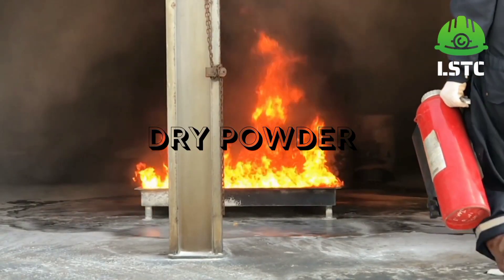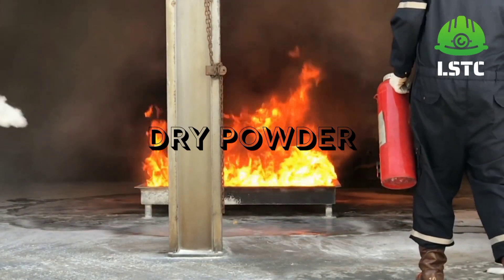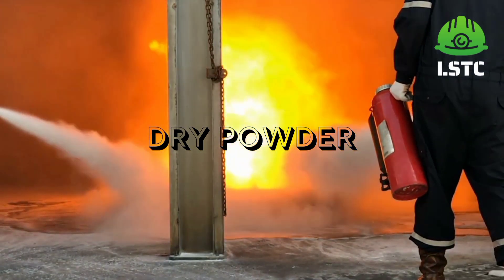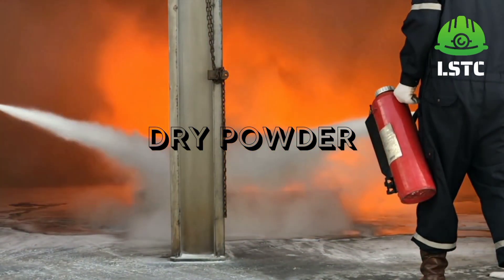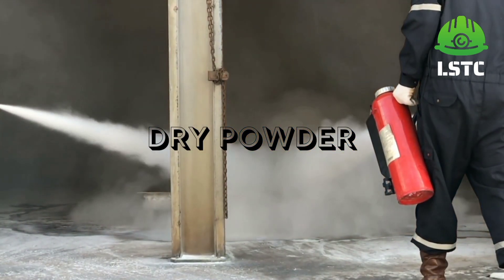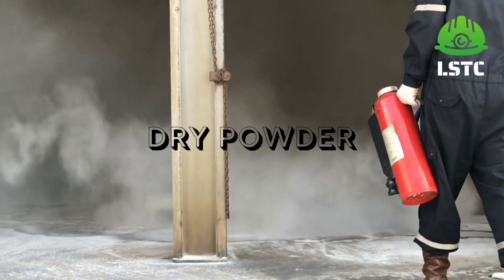Dry powder is suitable for all classes including electrical fires, with the exception of class F fire. It works by smothering the flames and may chemically interfere with the combustion process. It can be very messy and powder must not be inhaled. This is not recommended for use in confined spaces.